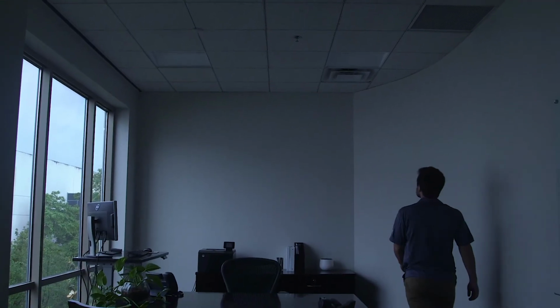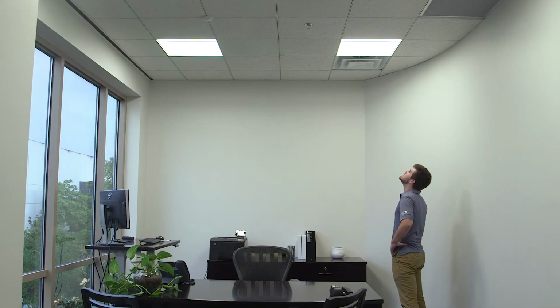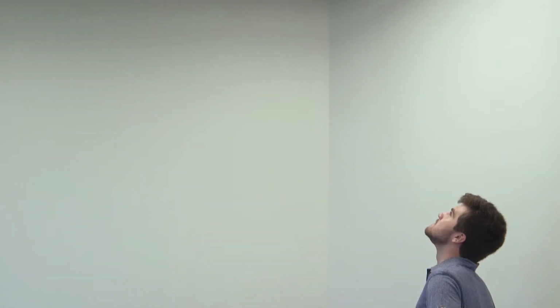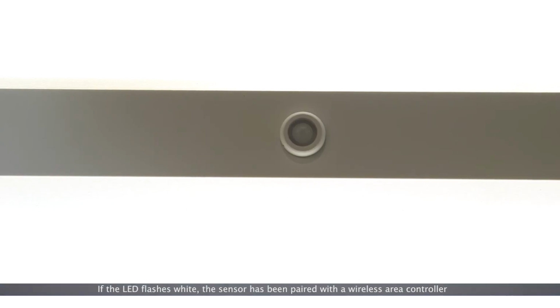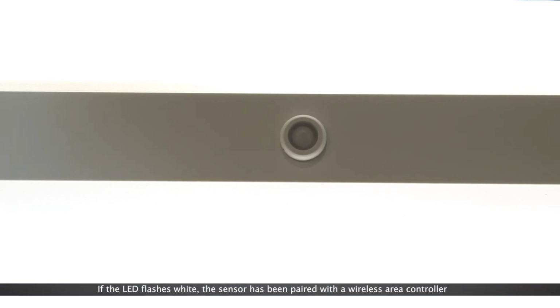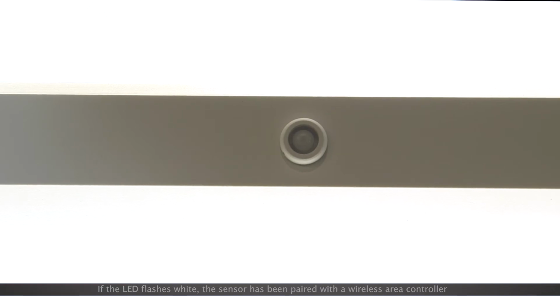Out in the space, walk under each fixture with integrated sensor or tile-mounted sensor and confirm that the lighting is on or turns on with the motion activity. Look at each sensor and confirm that the LED in the sensor's lens blinks green with the motion activity.